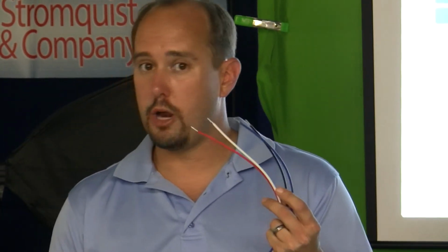Typically, by NEC code, how our product works is you have a cable so we can pick up voltage. It's probably hard to see the cable, but we ship a cable where you tap onto a breaker, and this allows us to see the true voltage of a system. So we're not estimating. There are some energy monitoring products out there that you put on CTs, and then you say I have a 480 volt system or a 208 volt system. The problem with that is we all know AC voltage fluctuates up and down constantly. So guess what happens with your power? It fluctuates up and down constantly. This allows you to really see what's happening. It also keeps the system very clean.